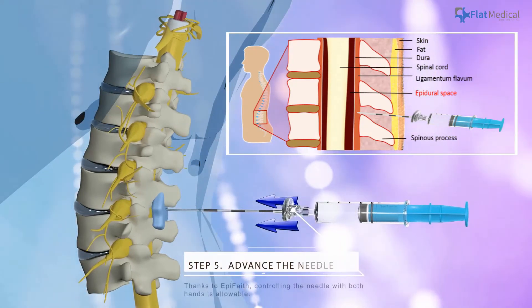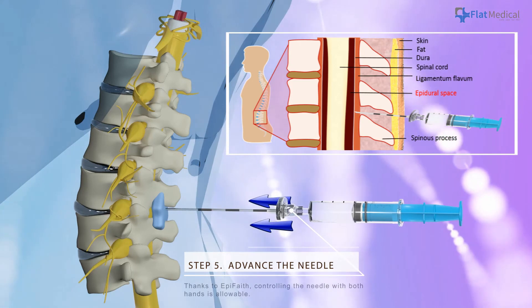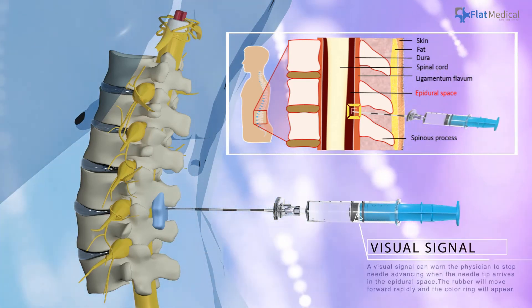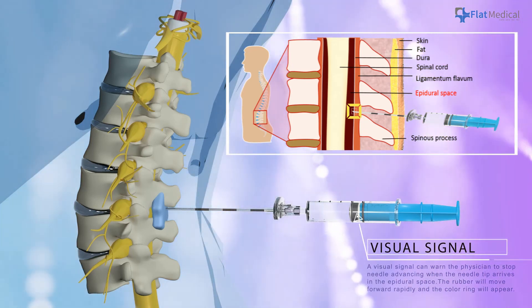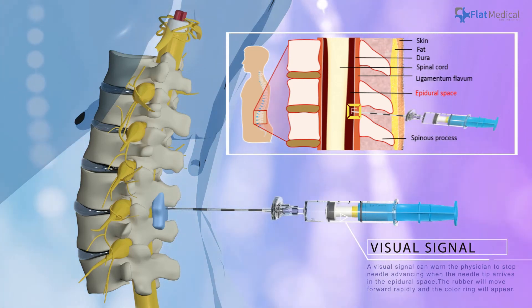Advance the needle. Thanks to EpiFaith, controlling the needle with both hands is allowable. A clear signal can warn the physician to stop needle advancing when the needle tip arrives in the epidural space. The rubber will move forward rapidly and the color ring will appear.